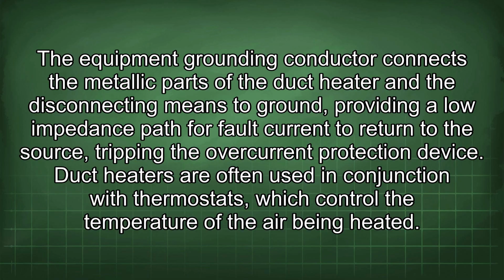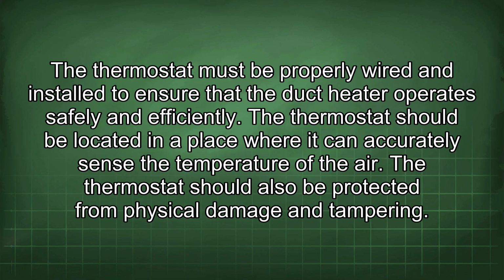Duct heaters are often used in conjunction with thermostats, which control the temperature of the air being heated. The thermostat must be properly wired and installed to ensure that the duct heater operates safely and efficiently. The thermostat should be located in a place where it can accurately sense the temperature of the air. The thermostat should also be protected from physical damage and tampering.